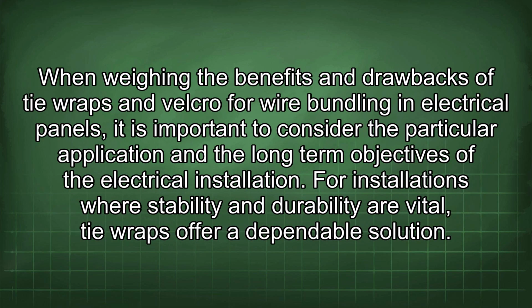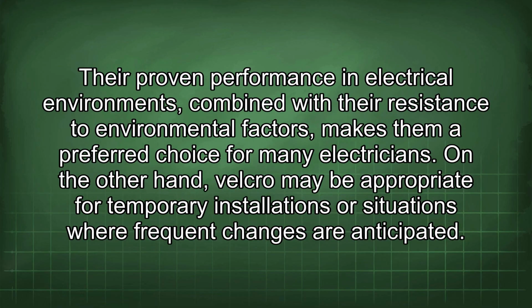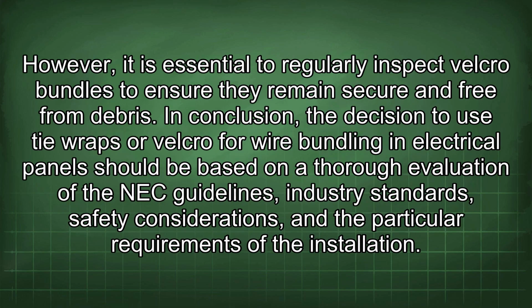When weighing the benefits and drawbacks of tie wraps and Velcro for wire bundling in electrical panels, it is important to consider the particular application and the long-term objectives of the electrical installation. For installations where stability and durability are vital, tie wraps offer a dependable solution. Their proven performance in electrical environments, combined with their resistance to environmental factors, makes them a preferred choice for many electricians. On the other hand, Velcro may be appropriate for temporary installations or situations where frequent changes are anticipated. However, it is essential to regularly inspect Velcro bundles to ensure they remain secure and free from debris.